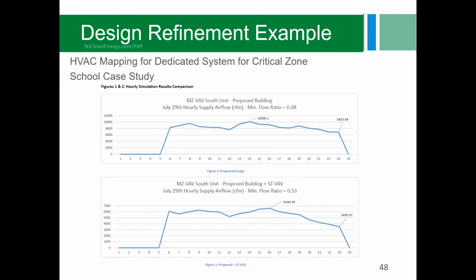And this is just a graphical depiction of the minimum flow ratio, the top graph, when the workshop was part of that multi-zone VAV system. So the minimum fan ratio only dropped to 0.68. Once we removed the workshop from that multi-zone system and gave it its own single zone system, the fan ratio was able to drop to 0.53 for that multi-zone system. So good savings, good results. So that's an example of design refinement.